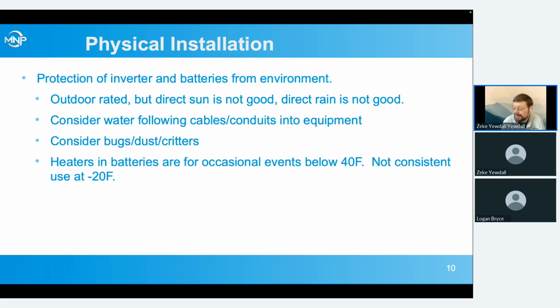If you have to put them outdoors on a wall, an east or a north facing wall is a lot better than a west or a south facing wall for that reason. And similarly, direct rain, yes, they're outdoor rated. But have you considered fully all the conduits going in and out? Are they waterproof? Are they sealed against water coming down cables and following the cables into the equipment? Do you have drip loops? Because you can get a lot of sources of water getting in the equipment other than just from the exterior, and conduits are one of those sources. Even air coming through a conduit from a warm building into a cold exterior cabinet can condense and put a lot of water into the inside of equipment.